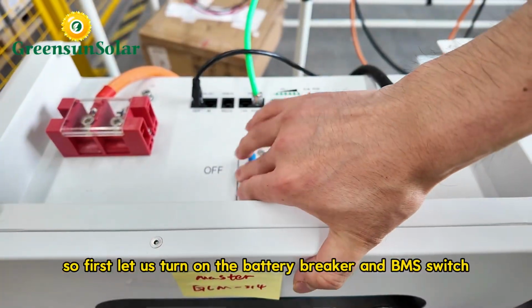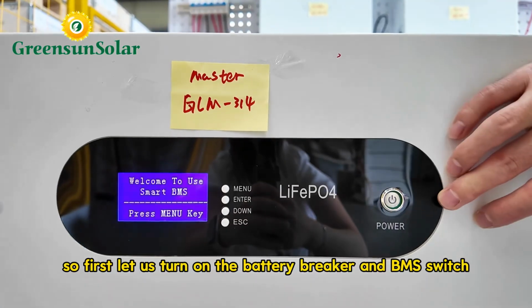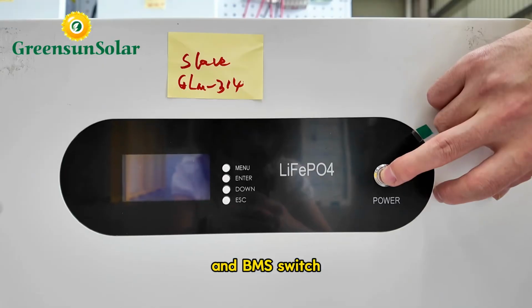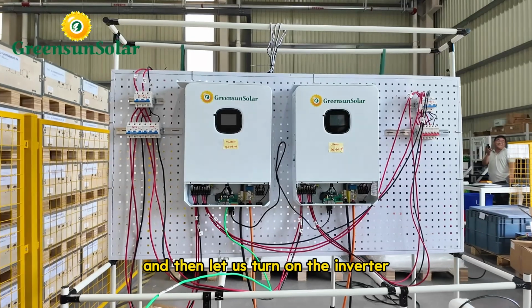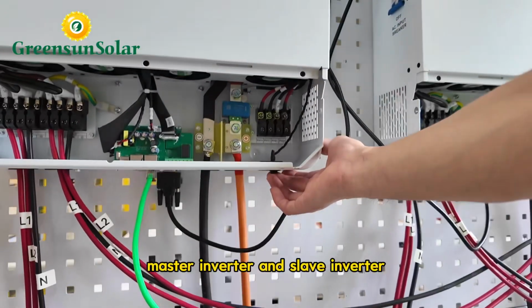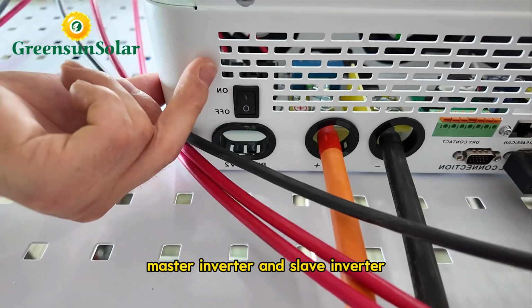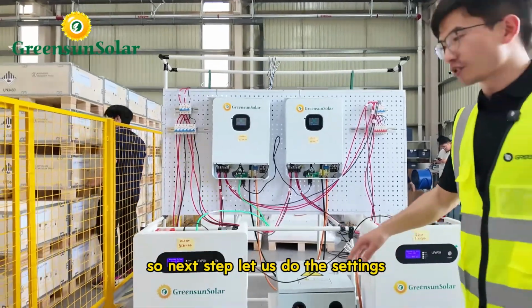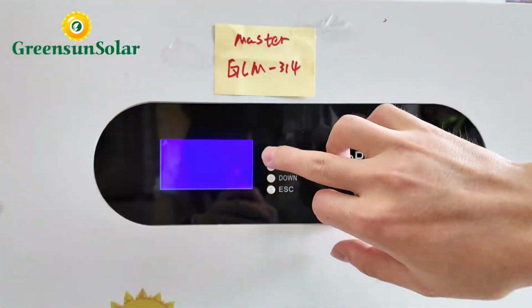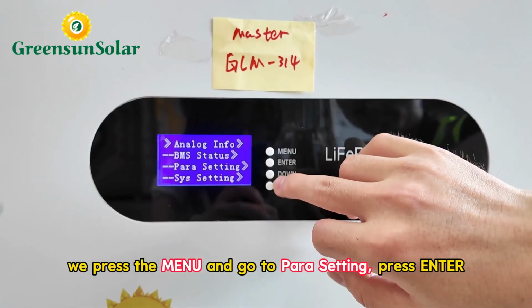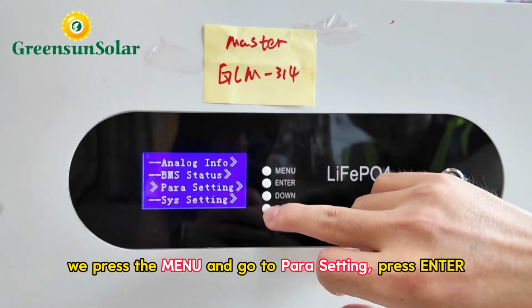So first let us turn on the battery breaker and the BMS switch, then turn on the slave battery breaker and the BMS switch. And then let us turn on the master inverter and the slave inverter. So next step, let us do the settings. We press the menu and go to parameter setting.